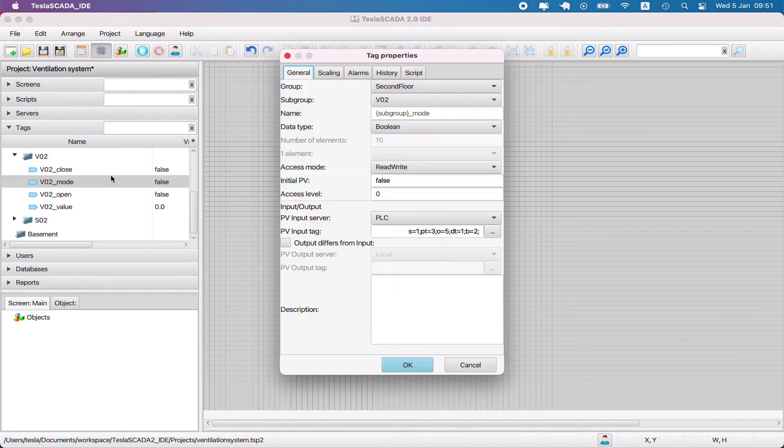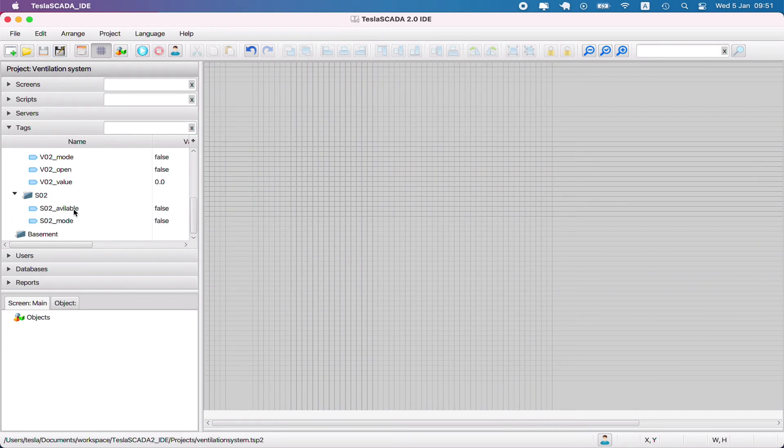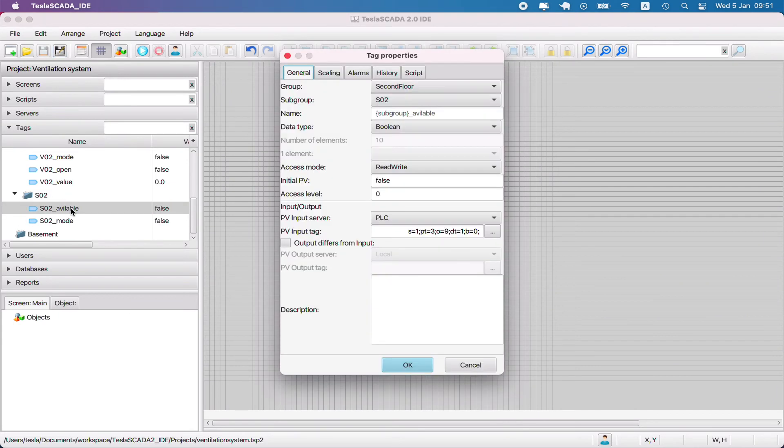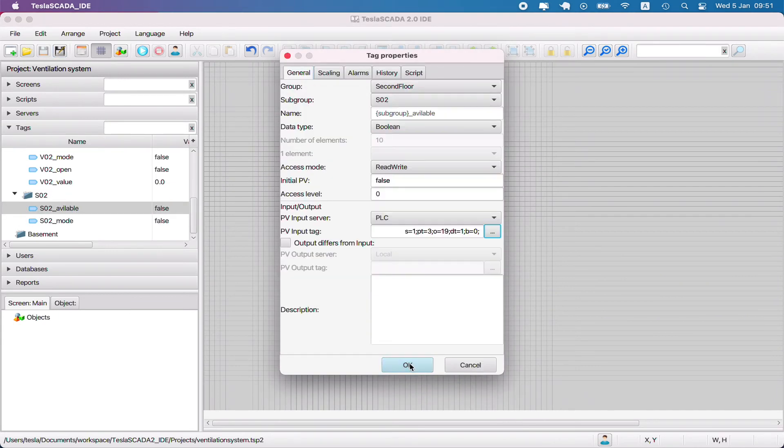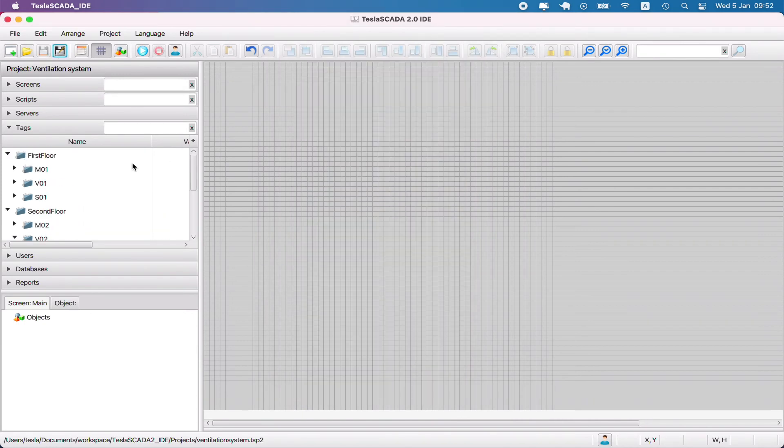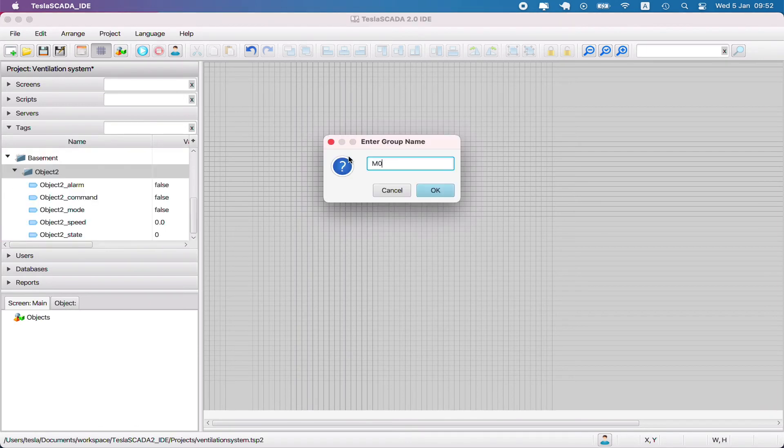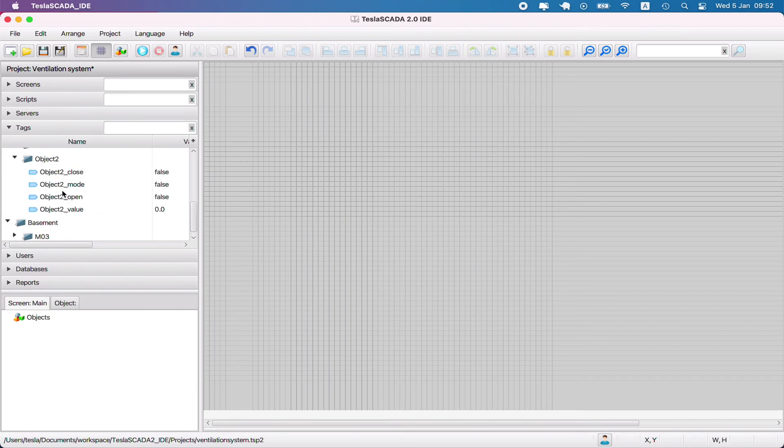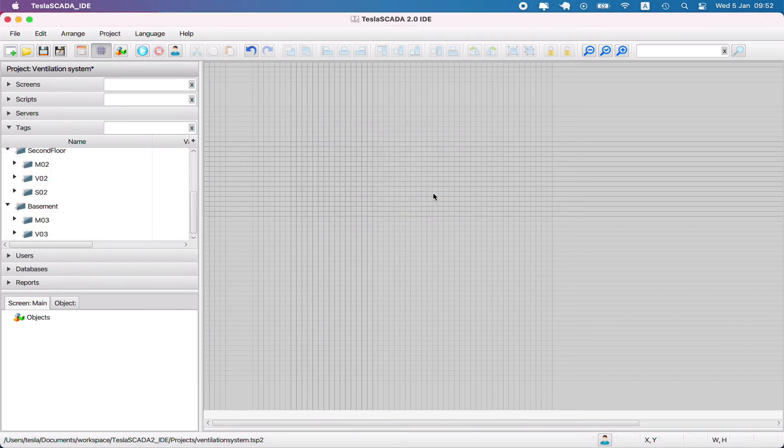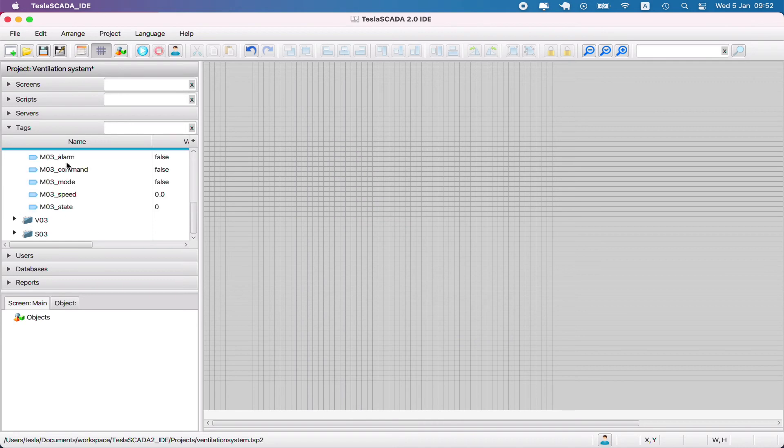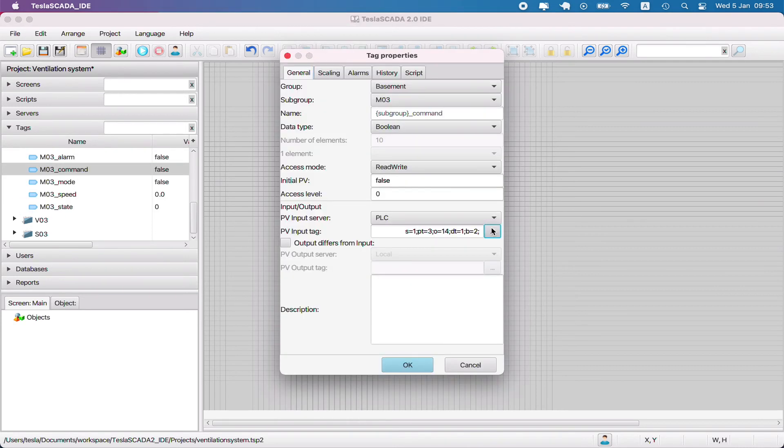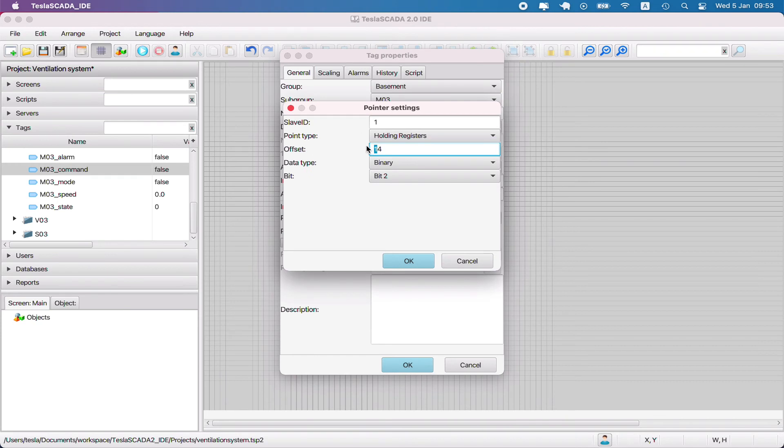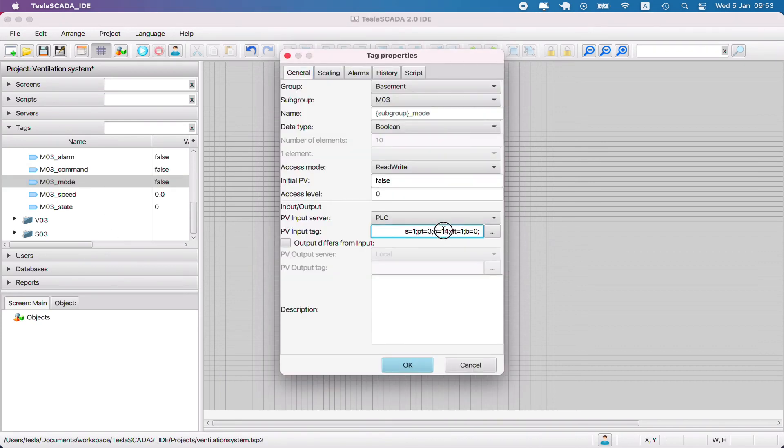You can do it only manually for Modbus register. But if you use some other servers like OPC UA, it's possible to bind the name of the tags to the name of the nodes that bind to the OPC UA server. But in our case we make it manually. We simplify this only by changing subgroup names, and in this case the name of the tags are changed also, but Modbus registers we have to change manually.